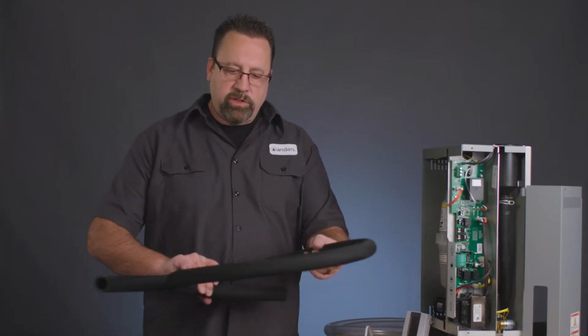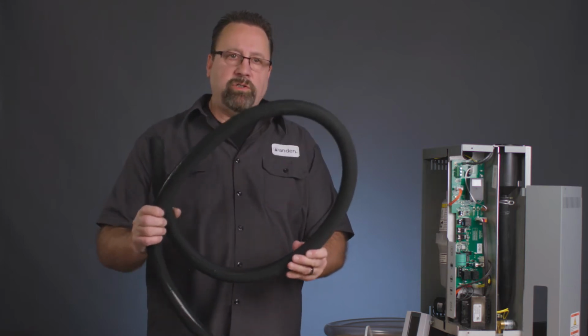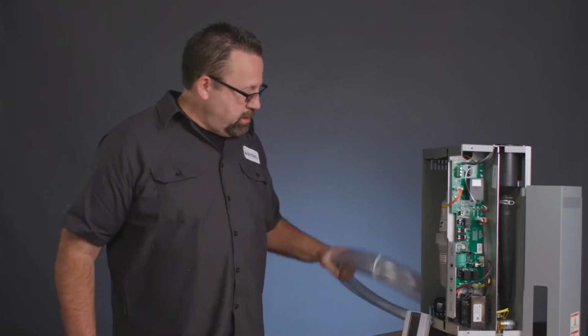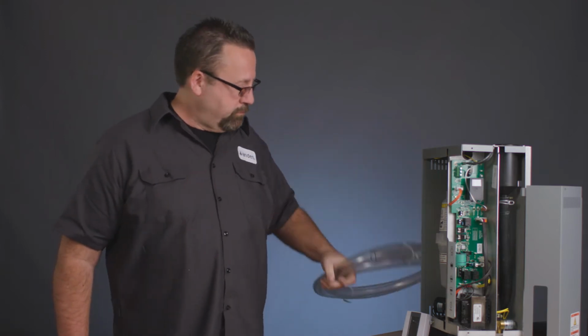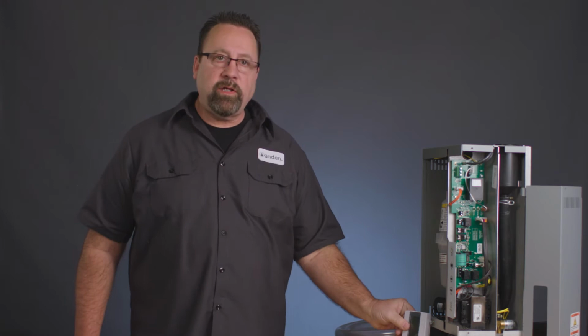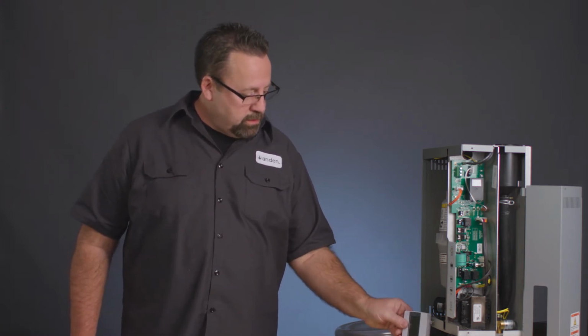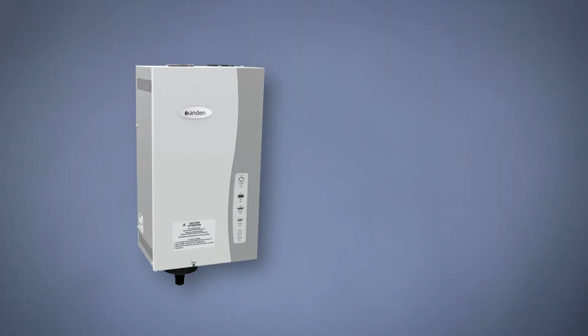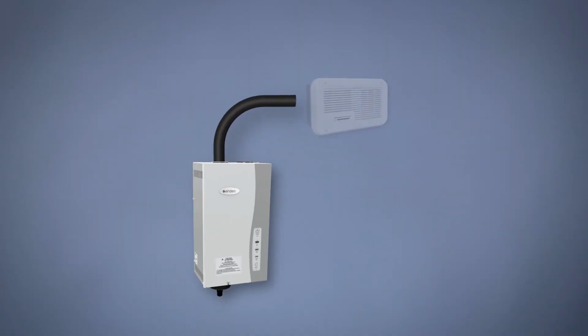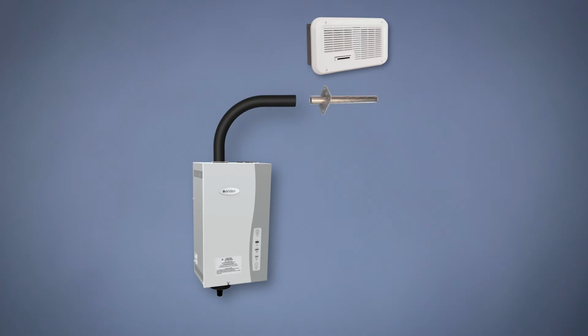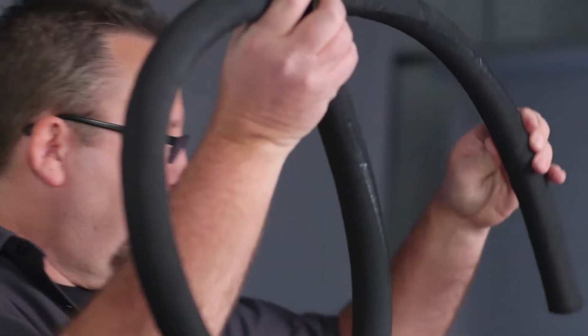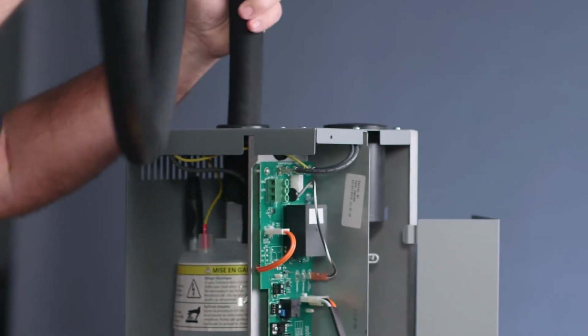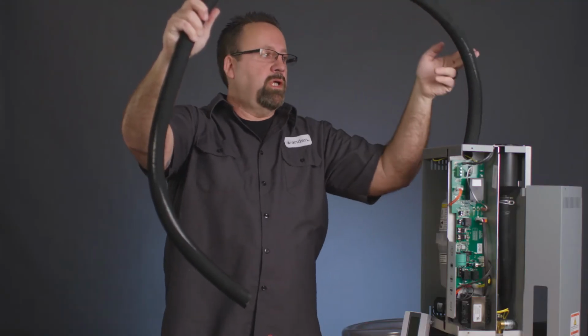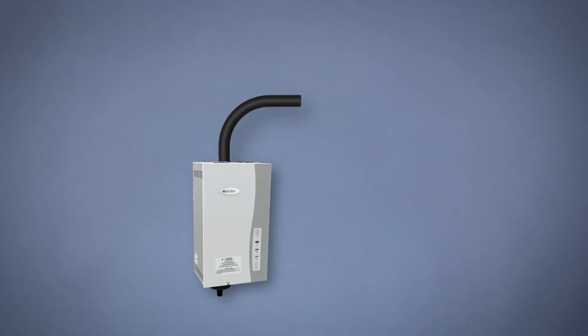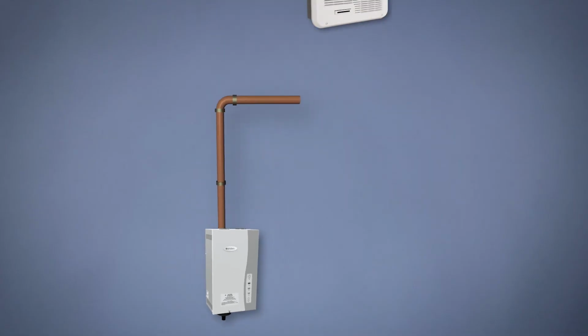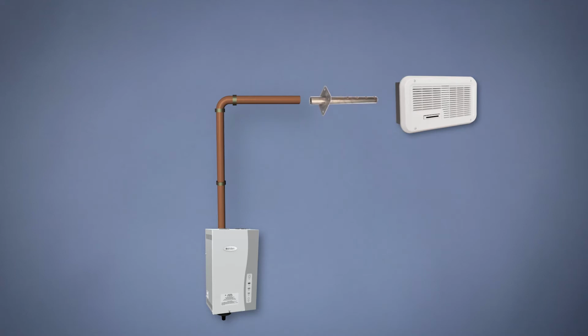The steam humidifier comes with 6 feet of very heavy-duty industrial marine-grade steam hose, 10 feet of drain tubing, the model 5558 control, and either the fan pack or the steam dispersion tube. The steam hose is going to either connect to the fan pack or the steam dispersion tube that goes to the HVAC system. The steam hose goes in and hooks right to the canister. And so we can cut this to whatever length we need. We can also run up to 20 feet using hard pipe copper if we had to go a long distance from the fan pack or steam dispersion tube back down to the steam humidifier.